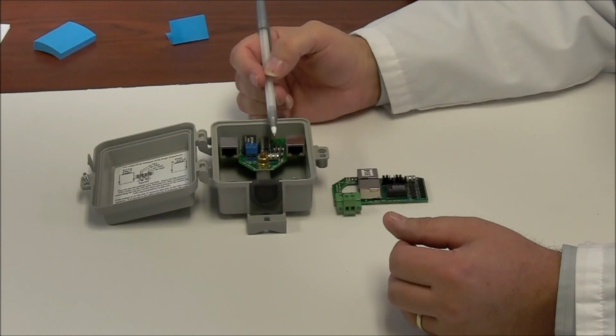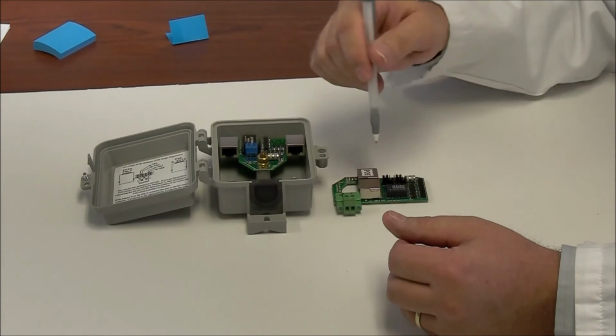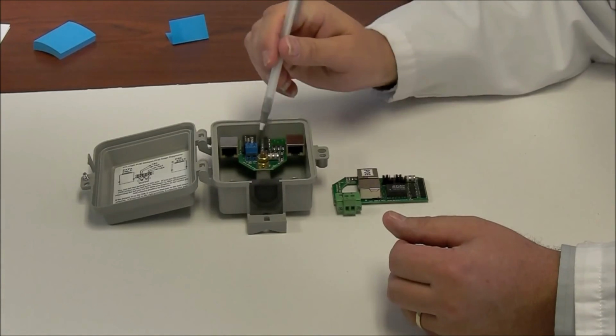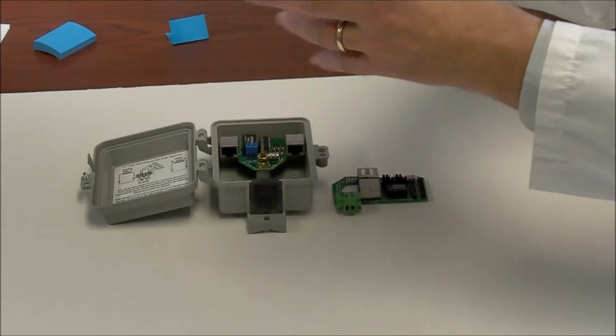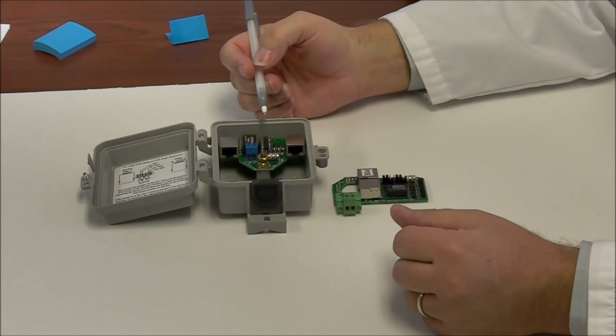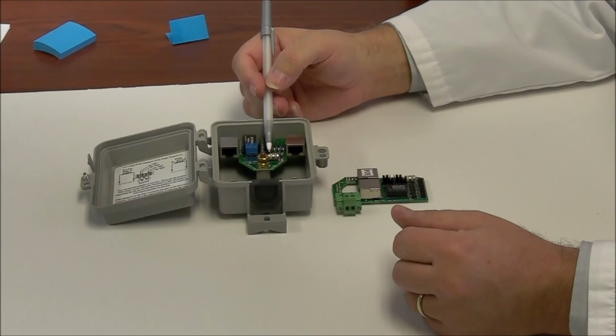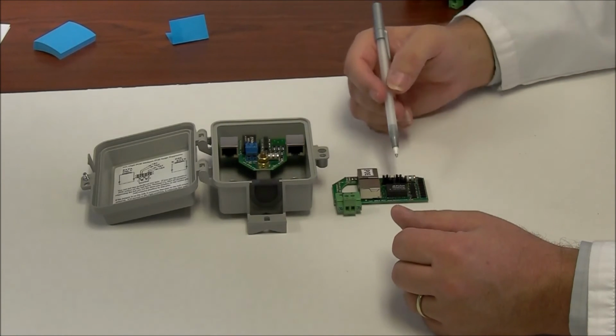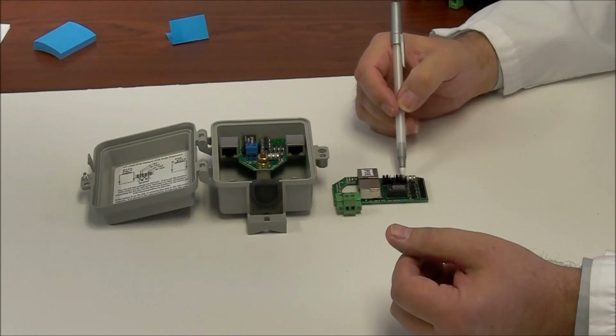The end metal plates are hooked up to the aggregate total. I've got steering circuitry on these things that funnel all of the surges down to the gas tube, down to the 2 ends of the gas tube surge suppressor, and the middle of the gas tube discharge device is connected to the ground lug.